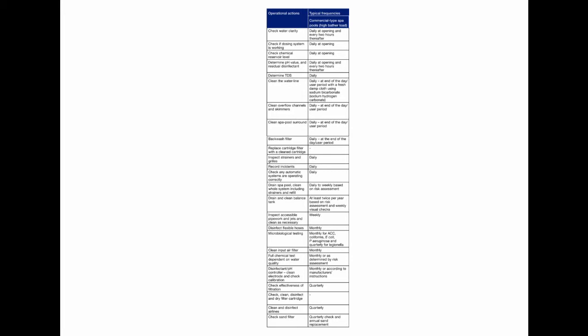What you should look to do as well, potentially for busy spa pools, is completely drain the entire tank and clean everywhere, including the strainers. That could be on a daily basis for busy commercial facilities, or if it's a quiet facility that could potentially be anywhere between daily and weekly, but that would need to be based on risk assessment.